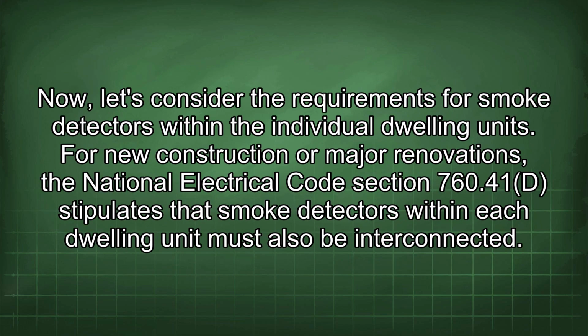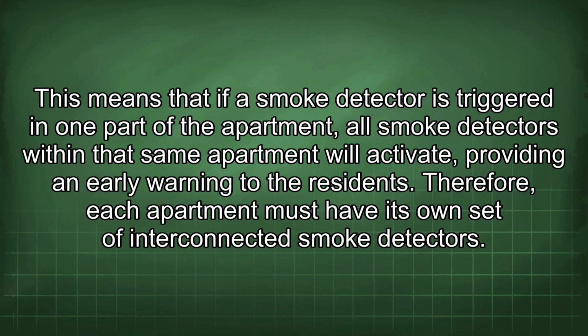Now, let's consider the requirements for smoke detectors within the individual dwelling units. For new construction or major renovations, the National Electrical Code Section 760.41d stipulates that smoke detectors within each dwelling unit must also be interconnected. This means that if a smoke detector is triggered in one part of the apartment, all smoke detectors within that same apartment will activate, providing an early warning to the resident.